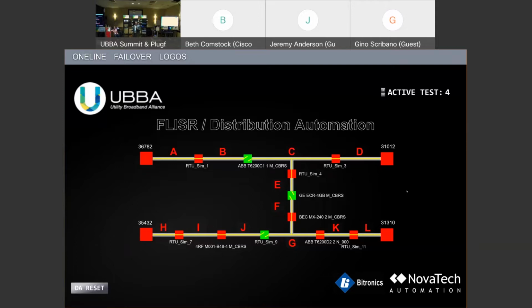Those used to be electromechanical devices that were magnetic predominantly. Now we put sophisticated controllers on them, like these blue boxes, and these boxes are measuring the currents and voltage waveforms in real time, and we give them a setting value and say, hey, if you go over this for a certain amount of time, so a time over current function, typically, and there's other functions in there, you're going to do something about that. And we can decide, hey, if it's a really big fault and it occurs really fast, we might do something differently than if it's a small fault that lasts for a longer period of time.